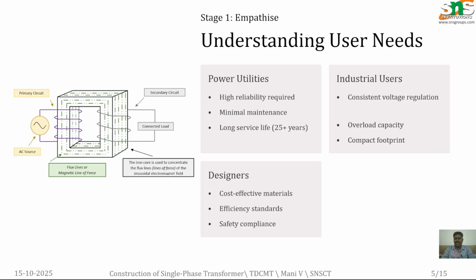First, while empathizing about the construction of a single phase transformer, according to the user need, the reliability should be very high. Why is high reliability required? And what about the maintenance requirement? Whether you expect minimum maintenance or maximum maintenance, and how long it will work, that is, the lifespan. These are according to the power utility. The industrial users will consider the voltage regulation, the overload capacity, and the compactness.